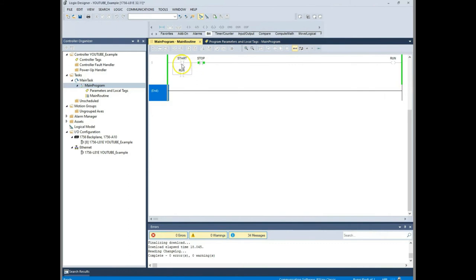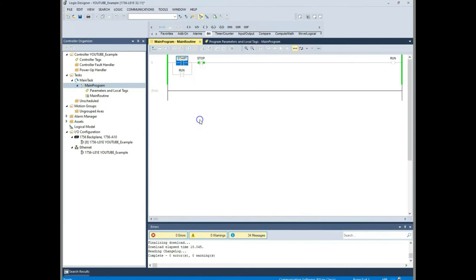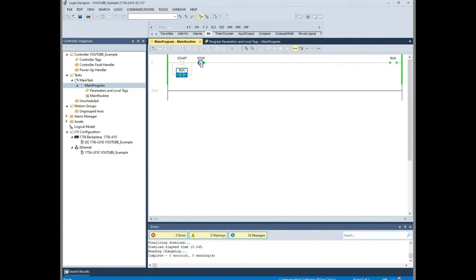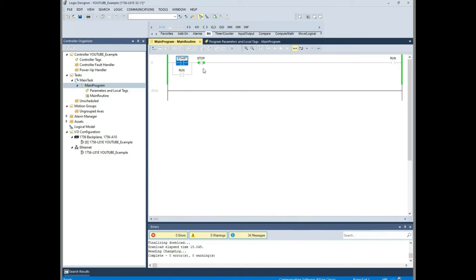Now we're running here. What I'm going to do is I'm going to toggle this bit by - you can either get control T or right click the bit and go to toggle bit. So I toggled it on. Motor is running. But now watch what happens when I toggle this off. My motor stays running. See that? Because I've got this path now that goes through and it's going to stay running until I toggle my stop. Once I toggle my stop, my motor stops running and it waits for me to hit start again. That's the way a seal-in circuit works. Now if I can do this fast enough, it only takes a millisecond to start that motor. So let me stop it a second. The same is true as stop. So I'm just going to toggle this super quick. Now you didn't see that start come on, but notice it's running. That's real important to remember whenever we do future programs. But this is our simple seal-in circuit.